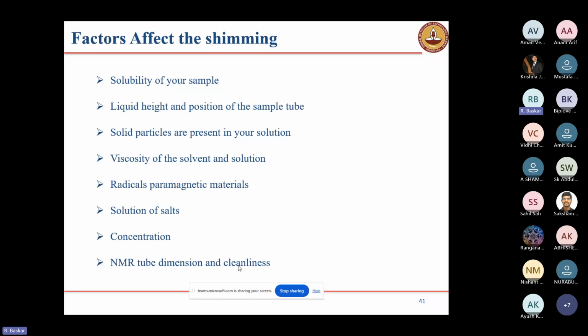Once shimming is done, then we have to give the radio frequency pulses. Then we have to start the acquisition. Before starting the acquisition, we have to check the following things. One is the pulse sequence. What are the experiments we want to do? We have to choose the proper pulse sequence. Next one is the acquisition time. We have to give the proper acquisition time. If you are not giving the proper acquisition time, we will not get the NMR signal.